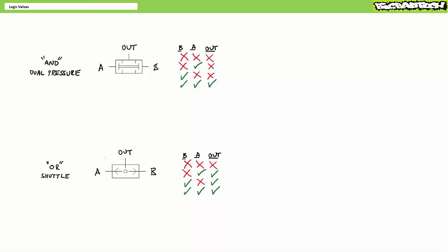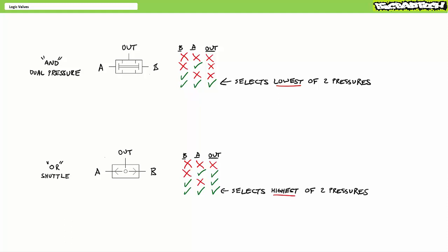Beyond the logical operation of these two valves, they also exhibit pressure selection. When both air pilot A and B are present for an AND valve, the AND valve selects the lowest of the two pressures. Whereas when both air pilot A and B are present for an OR valve, it selects the highest of the two pressures.